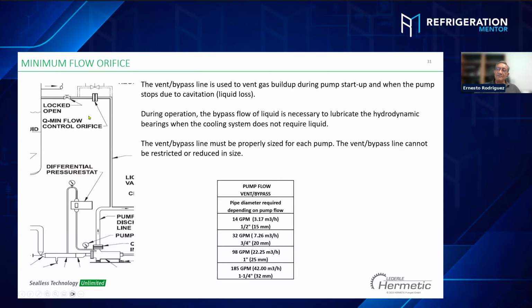Different pump manufacturers use a hand expansion valve. The difference with a hand expansion valve is sometimes it's too wide open. It's sending too much liquid back to the vessel, and you have a lack of liquid on the system. This is the reason the German Hermetic prefer to use an orifice versus hand expansion valves. Okay, so that's a good point.